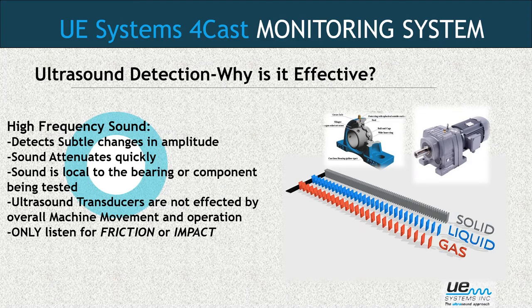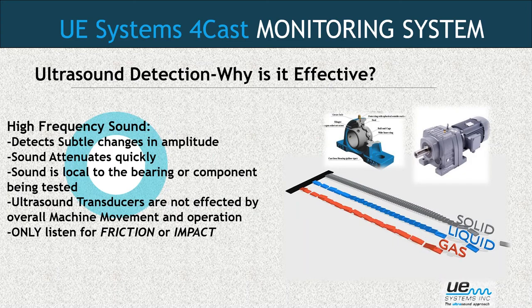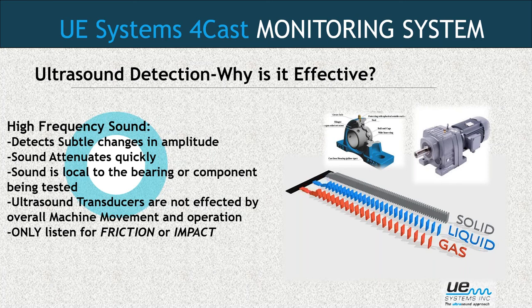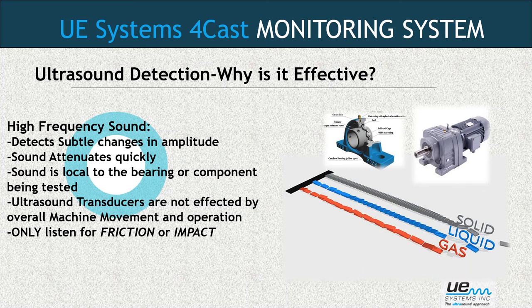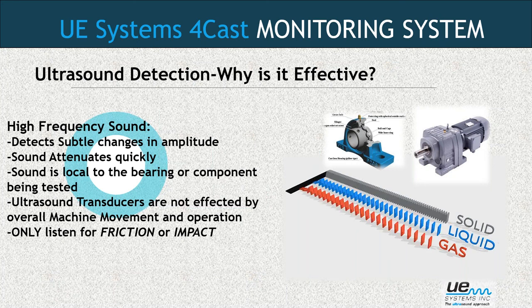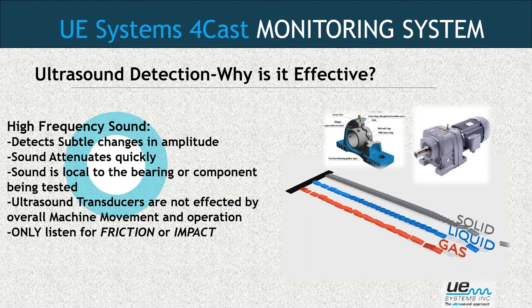Okay, the other part that makes ultrasound a nice technology for rotating equipment is that these ultrasound transducers aren't affected by the overall machine movement and operation. They're only listening internally for that friction or that impact. So ultrasound has become over the years a real go-to technology, especially on high overall vibration equipment, where you would get a lot of false readings from other technologies. Ultrasound can be mounted permanently on the housing, and it'll even move in unison with a high vibration piece of equipment. Even something like a shaker, you can mount a transducer on, and we're still only listening for that friction or that impact.